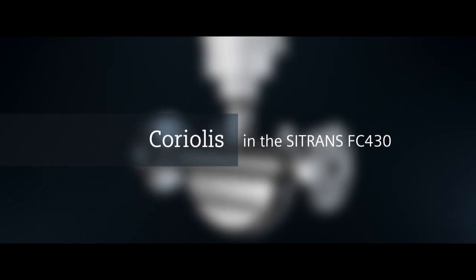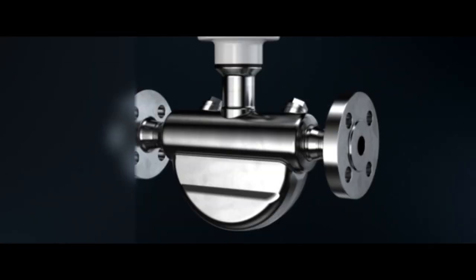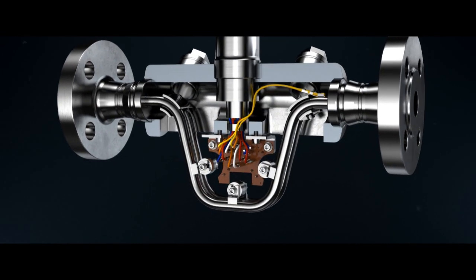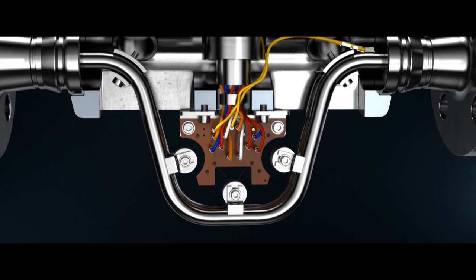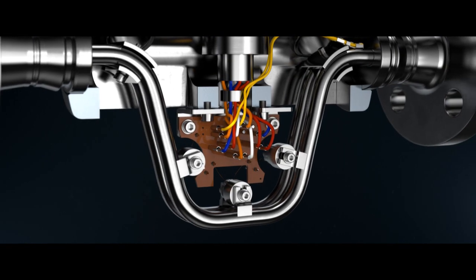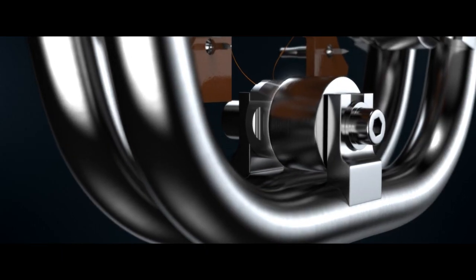The Siemens Sitrans FC 430 flow meter functions according to the same principle. Two symmetric metal tubes are set vibrating. This is ensured by a driver coil in the central section.